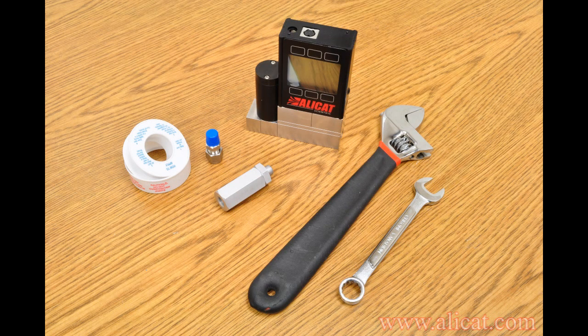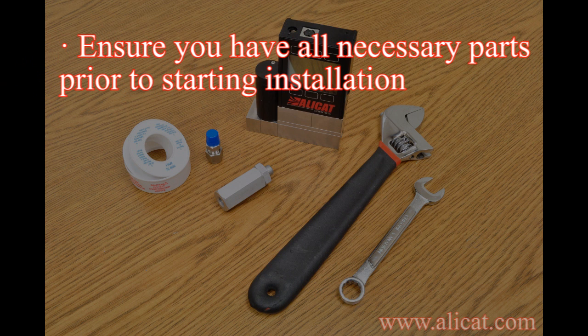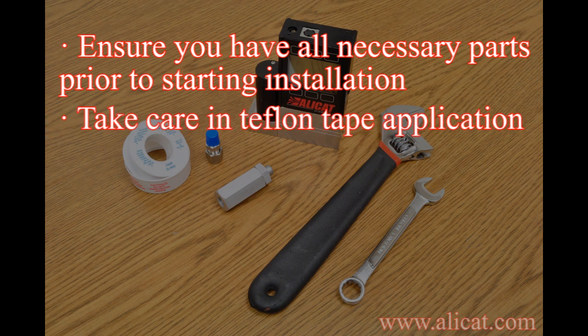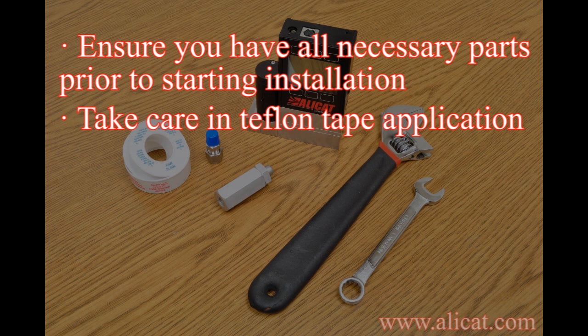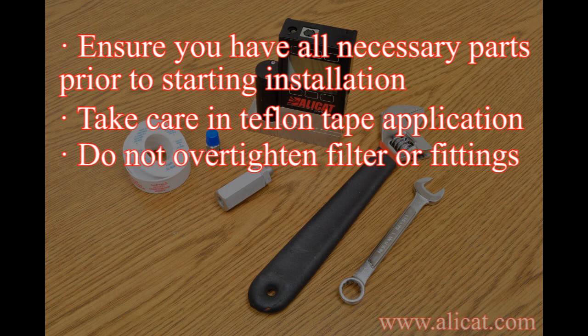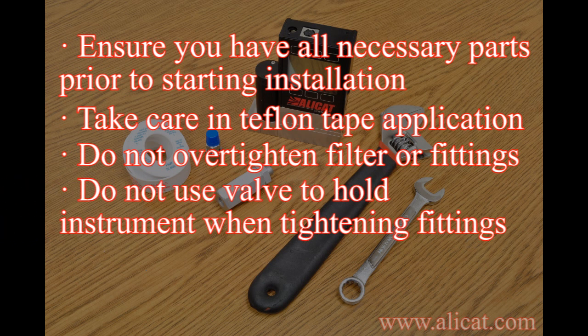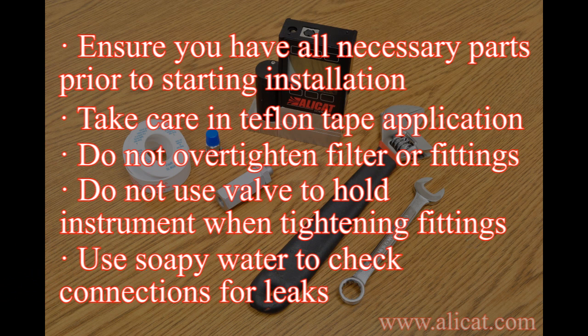In reviewing the key points in the video, please note the following. Ensure you have all necessary parts prior to starting the installation. Be mindful of proper Teflon tape application. Do not over-tighten the filters or fittings. Do not use a control valve as leverage when installing these fittings. Leak check all connections using a soapy water solution.